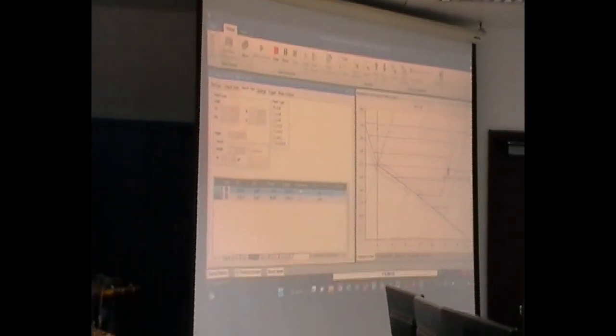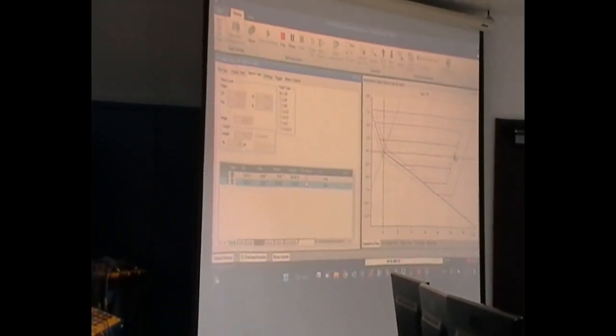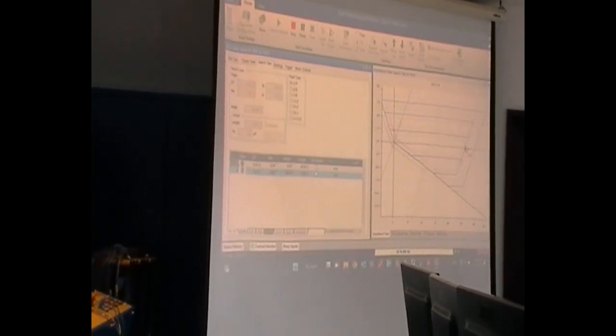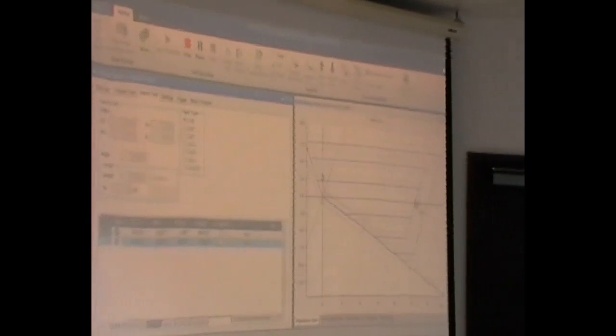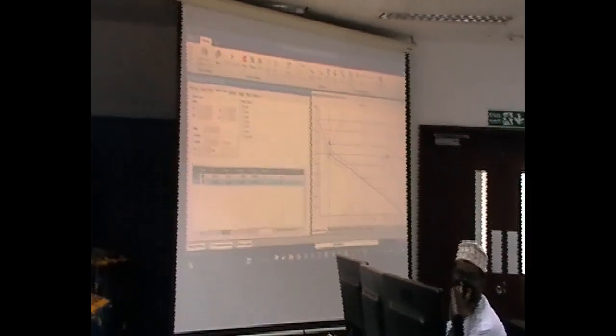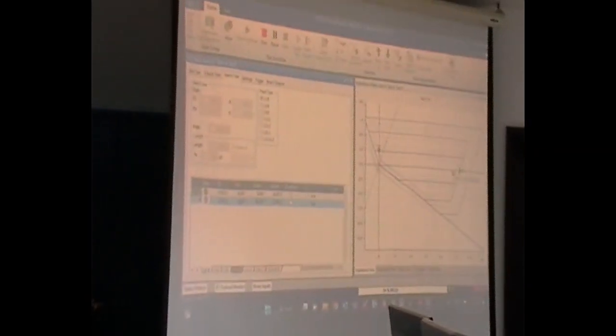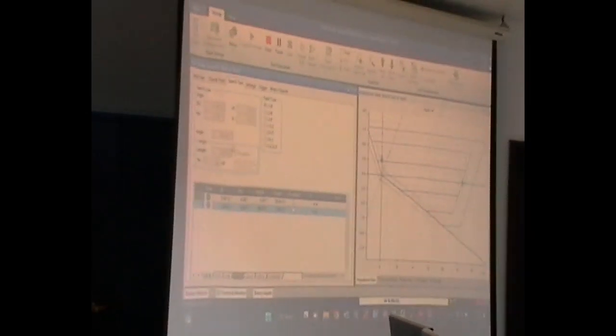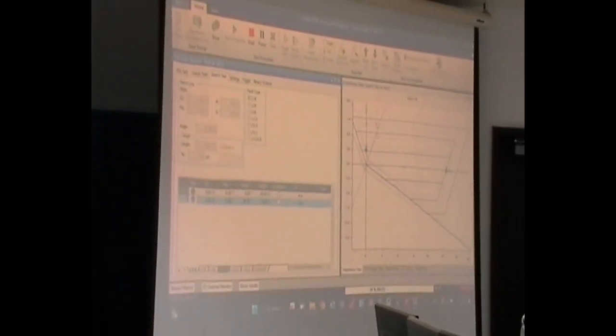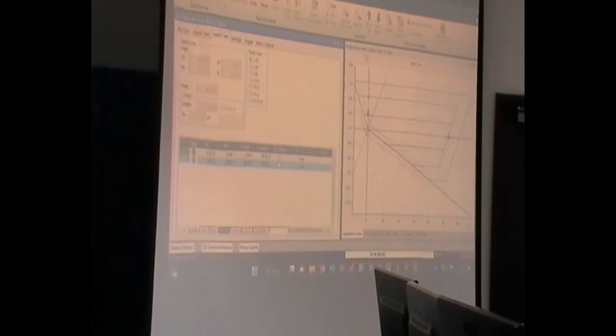This will take a little bit, like a minute, because it starts trying multiple points to get it right. It will inject a little bit before the line, and it will go slower, slower, slower to reach the line automatically and see where the exact number is. This is an automatic operation. I only have to select the line where I want to inject. Very simple. I've already selected this line at 90 degrees, 0, 0. So it's basically here and here.